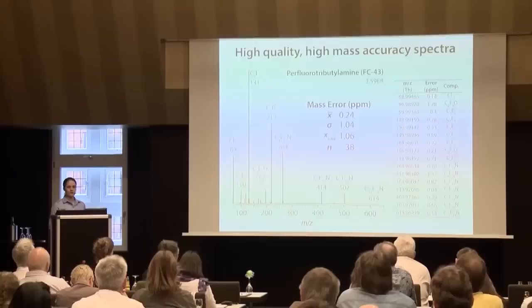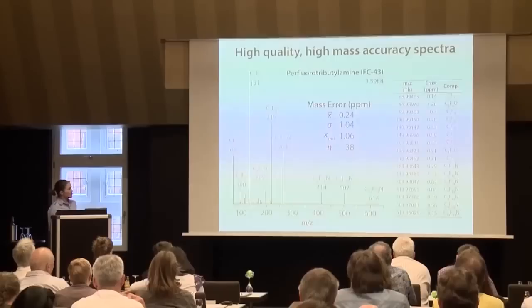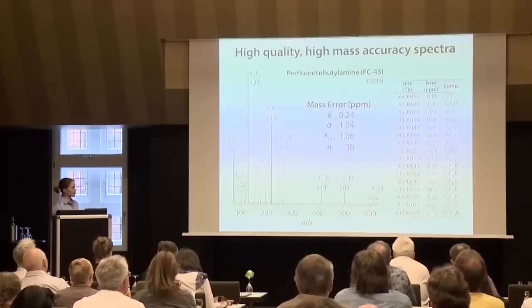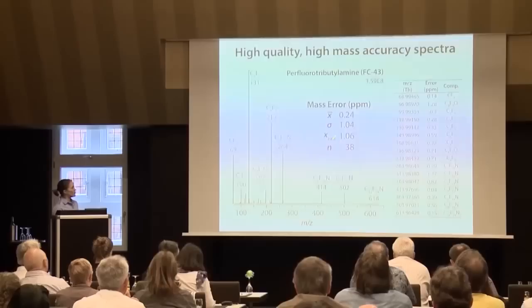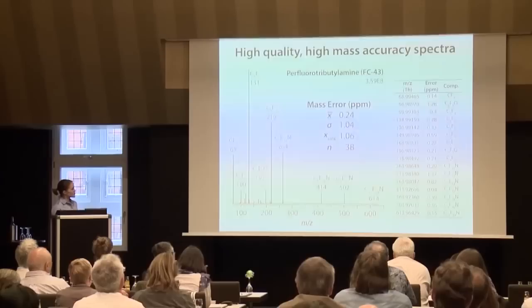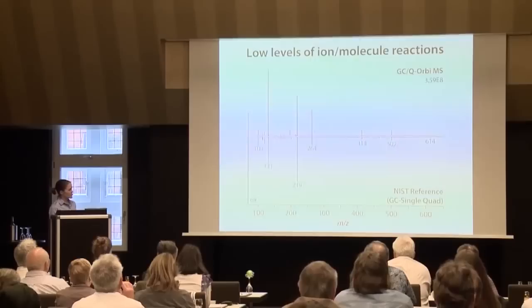The first thing we looked at was the spectrum of FC-43 — probably all know and love this compound. Here is a typical spectrum from the GC quadrupole orbitrap for FC-43. You should notice that we are operating with the same high mass accuracy as seen with other incarnations of the orbitrap mass analyzer, giving an average of less than 1 ppm. You can also notice relatively low levels of water reactions from trapping in the C-trap.